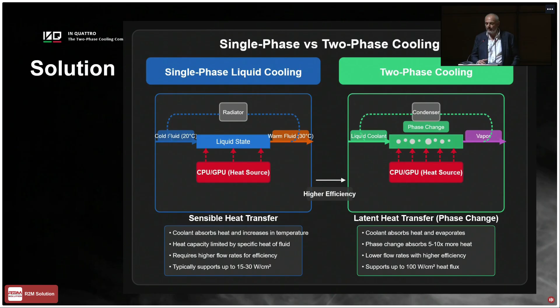And so heat generated by the processor leads to evaporation on the heat exchanger. So the higher the thermal power, the higher the quantity of vapor. If we compare this with liquid cooling system, where the heat is removed by increase of temperature of the liquid medium, we have that this new cooling technology is more efficient than standard liquid cooling technology. So this means lower flow rate, and this is a critical parameter. This is a very important parameter. And in general, a very high thermal power can be removed from processors.